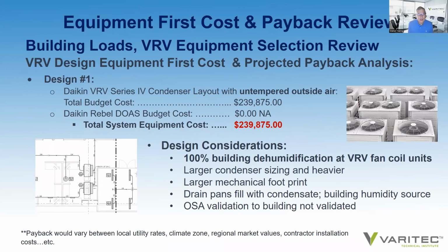If we look at the untempered outside air solution for design number 1, the variable refrigerant equipment alone, this doesn't include refrigerant piping or electrical or any of the supporting ductwork that is necessary, just the variable refrigerant equipment alone was $239,875. The reason for this price is because you have larger condenser sizing, the condensers are heavier, and you also have a larger mechanical footprint, which could influence your architectural design.